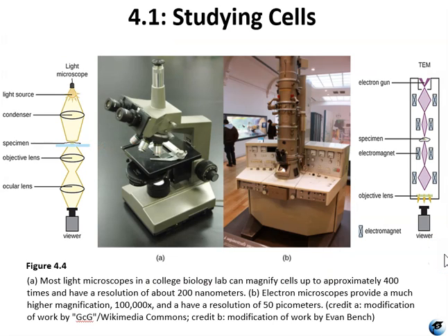In a light microscope, visible light passes and bends through multiple lenses to enable the user to see the specimen. Light microscopes generally magnify up to 400 or 1,000 times actual size. Magnification is the process of enlarging an object in appearance. This is not the same as resolution, which is the microscope's ability to distinguish 2 adjacent structures as being 2 separate structures. In other words, the higher the resolution, the better the image's clarity and detail will be. So this is how well it focuses.